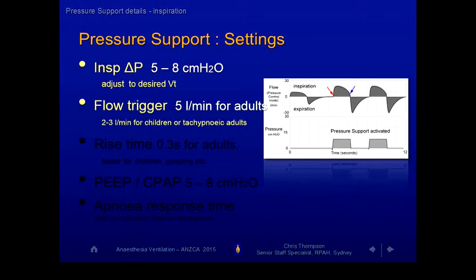There's a thing called a flow trigger, which is the sensitivity of the machine. If you set it too low, the machine might oscillate, vibrate, or self-trigger. But if your patient's gasping, that's a pretty high flow. What if it's a child making small tidal volumes? When they're very small, you might lower the flow trigger down. So for a 10 kilogram child, you might use a flow trigger of 1 or 2, something like that.